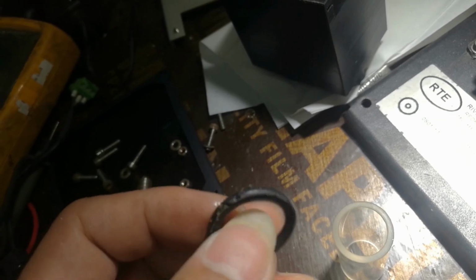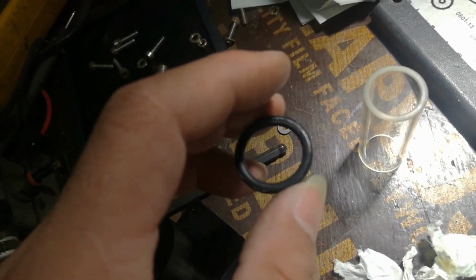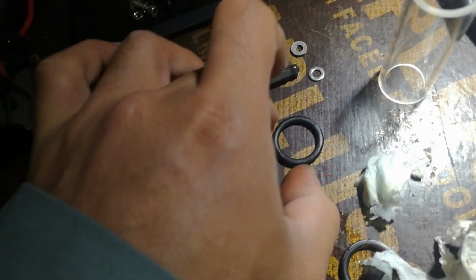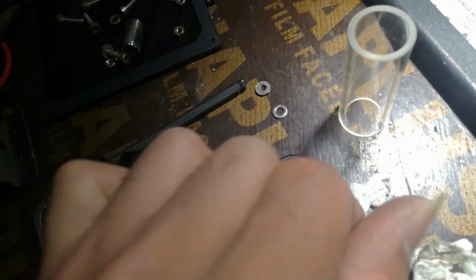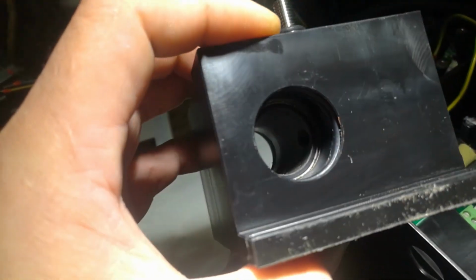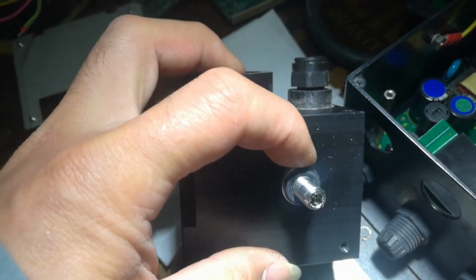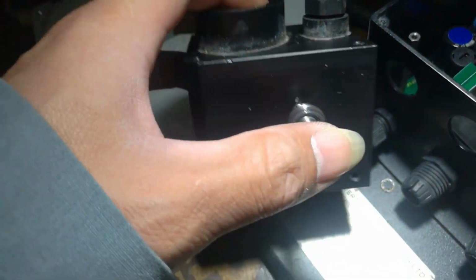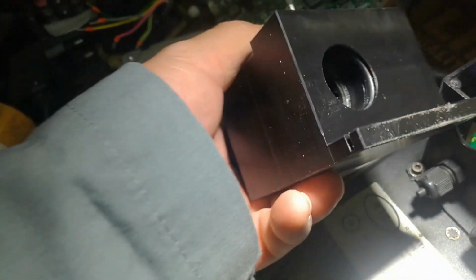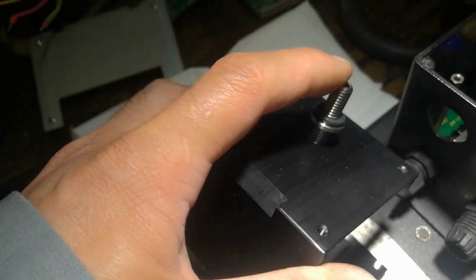So it gives you error already, because this is oily already. When this is inside, it will sense error in the sensor, because the element of the oil is passing through here, so it will sense all the time and give you error. So this one also, see, there is one hole inside. You see that hole? It passes through with this adjustment. This is a factory setting.